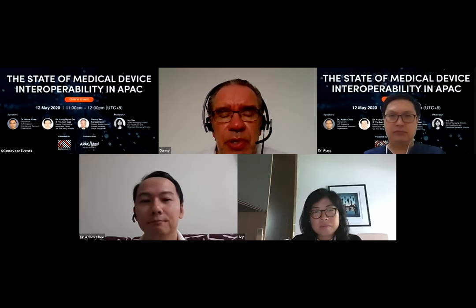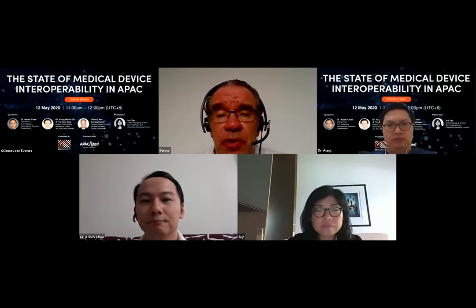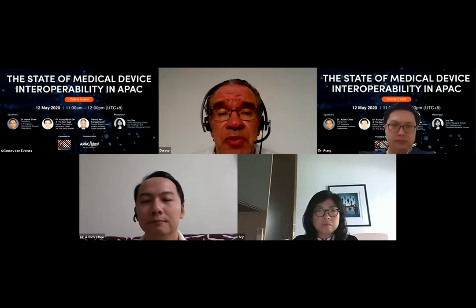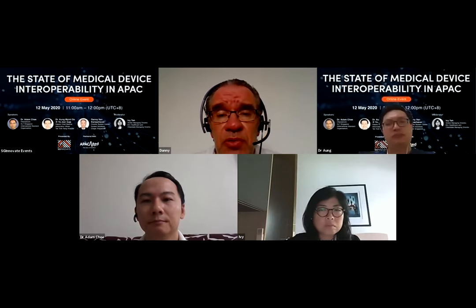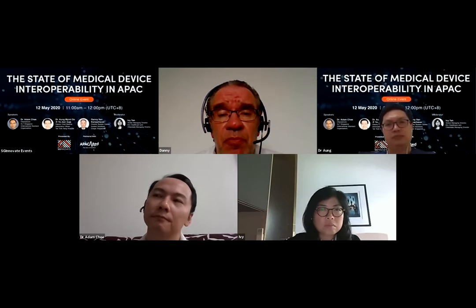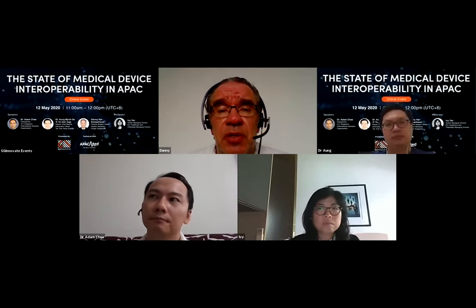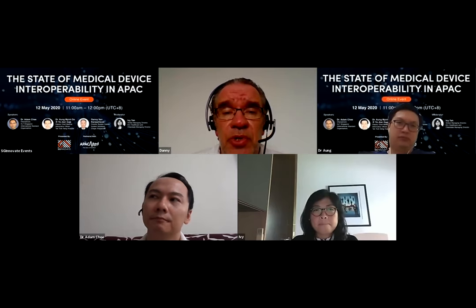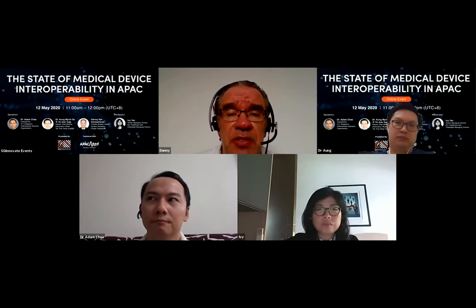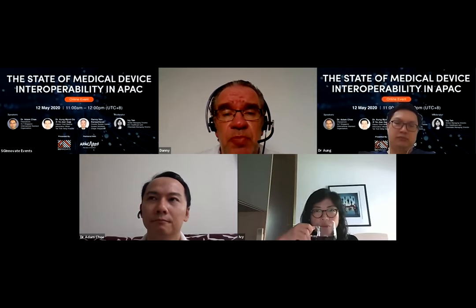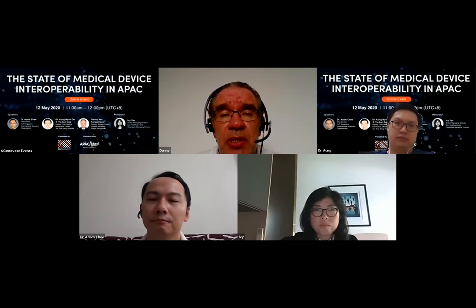So one point we're looking at, which is a pain for all hospitals worldwide, is alarm fatigue, and at the same time missing important alarms by the medical staff. Talking about COVID-19, where we see a huge increase in the use of isolation rooms, for vital monitors it's most of the time not a problem because they're all in a network with a central station at the nurse desk. But talking about ventilators and infusion pumps used close to the patient, the alarms don't go outside the isolation room.